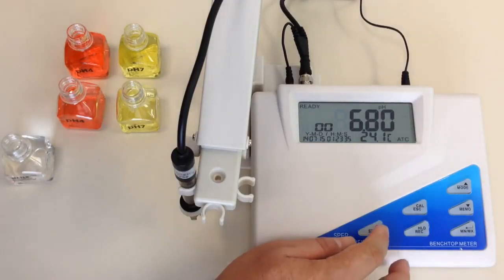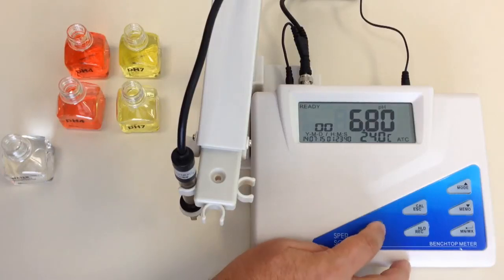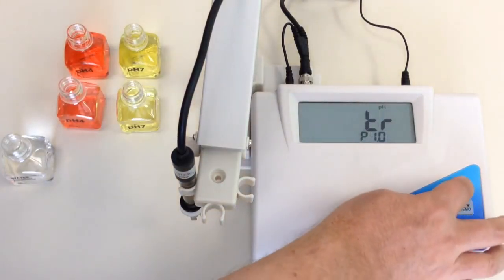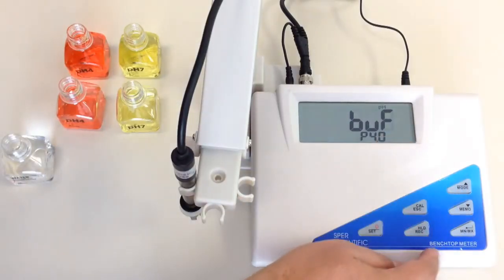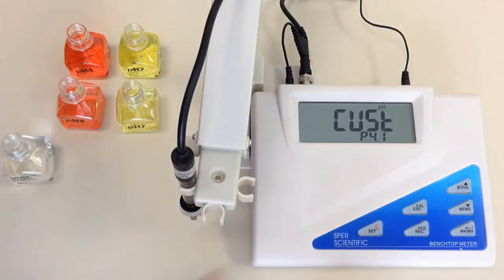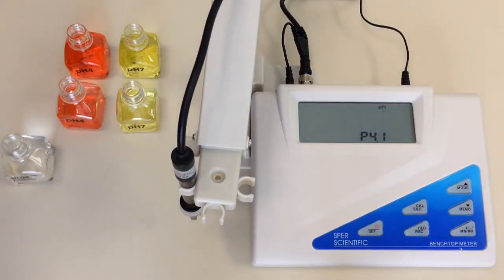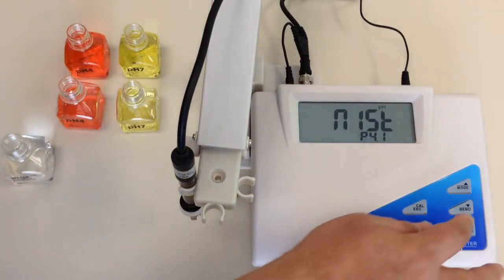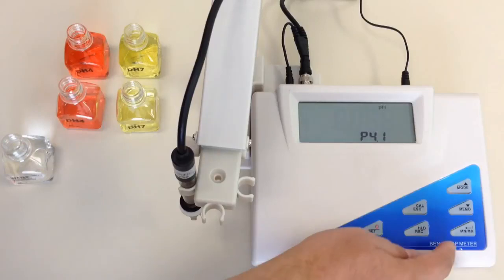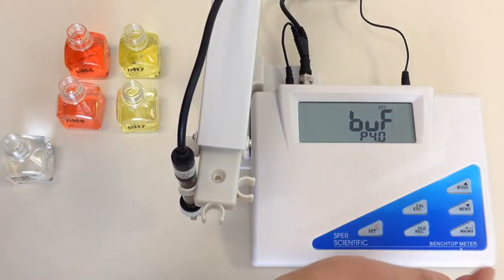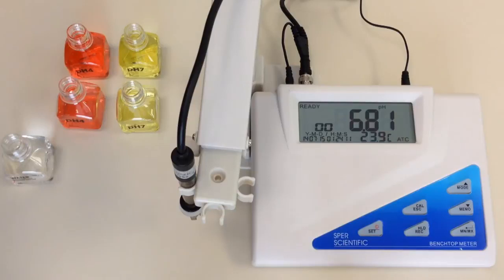So now I'm going to go in and check and see what is this particular meter calibrating to. I'm going to hold the set button down. I'm going to go into the P4 setting, hit min-max. So in this particular case, this meter is being set to what's called custom, which is your standard buffer solutions. If you saw it say NIST, then you know that it was calibrating to NIST buffer solutions. Since we are using standard buffer solutions, we want it to say CUS, or custom. Hit min-max, hit escape, and now I'm ready to calibrate.